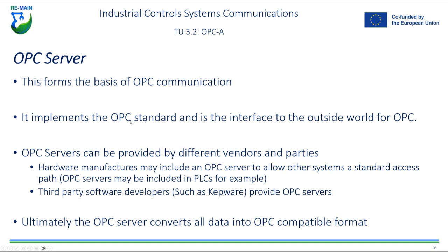Third-party software developers such as Kepware also provide OPC servers. The OPC server converts data from the PLC — the PLC might be communicating with field devices via Modbus, Profibus, Profinet, or other protocols — and converts all that gathered data into OPC-compatible format, so OPC clients can connect to the OPC server and retrieve the data they need.